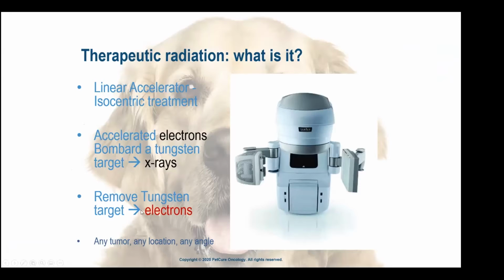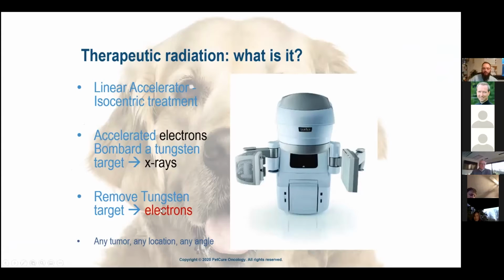If we remove that tungsten target, we've used these linear accelerators to treat with electrons. Because those particles are not as forward directed as photons, we can harness the energy, which comes out in a teardrop shape, and we can basically shape the field and treat superficial tissue. So with electrons, the benefit is that once it penetrates into dose, the dose fall off is very rapid, rather than, you can think of a photon.